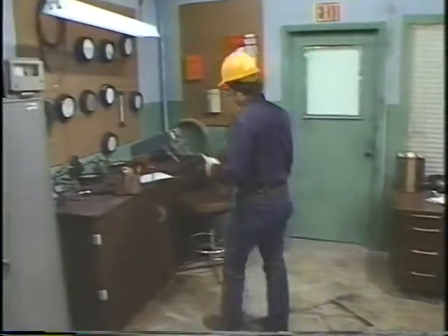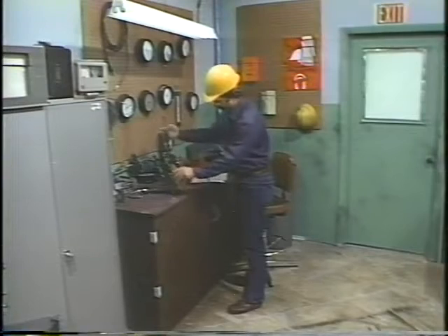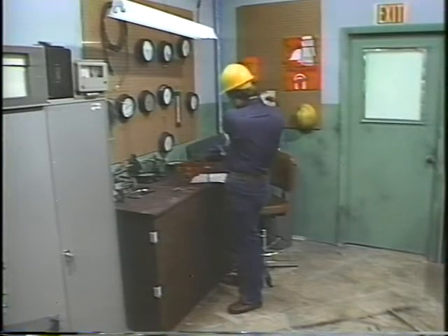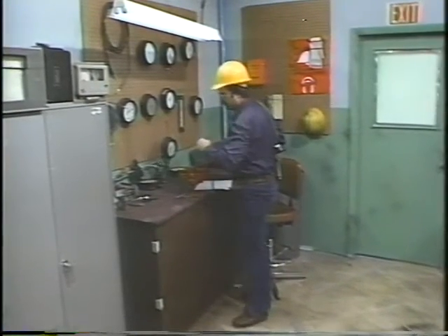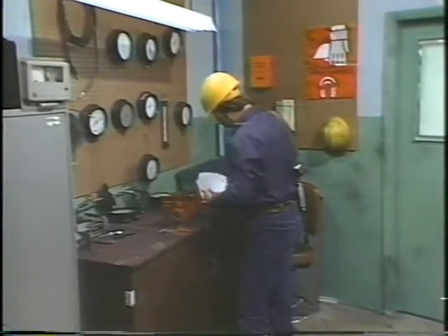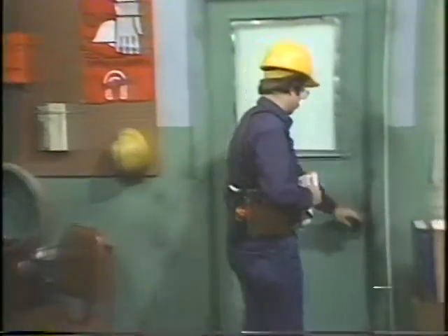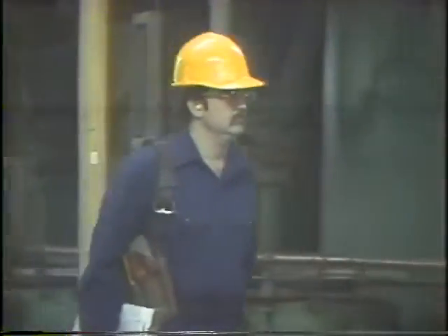Okay, I've got the control logic diagram. Let's see, what else do I need? I need to take my tool pouch and any special tools. Yeah, I should take some leak detector. I don't need any multimeters or any other electronic test equipment. The system's all pneumatic. And this ought to be enough to get me started. With the symptoms identified on the work order, there could be any number of problems. I'll have to go over the problem with the operator and see what he can tell me about how the system's operating now.